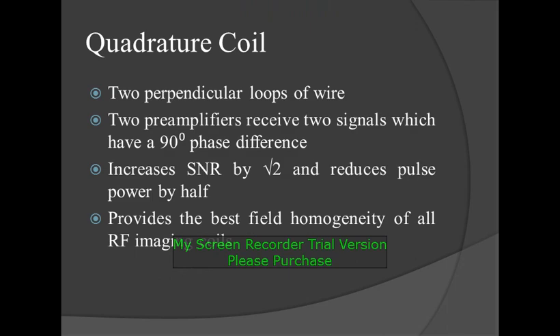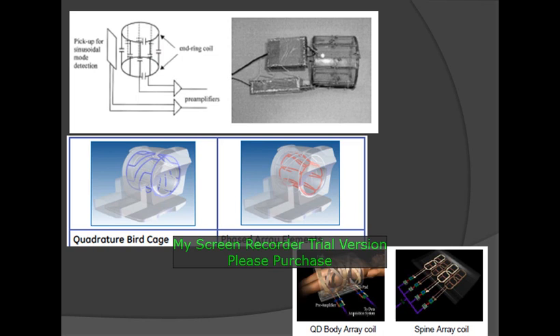Quadrature coil: two perpendicular loops of wires. Two preamplifiers receive two signals which have a 90-degree phase difference. This increases the SNR by a factor of root 2 and reduces the pulse power by half. It provides the best field homogeneity of all RF imaging coils. These are the birdcage coil phased array elements, the QD body array coil, and the spine array coils.